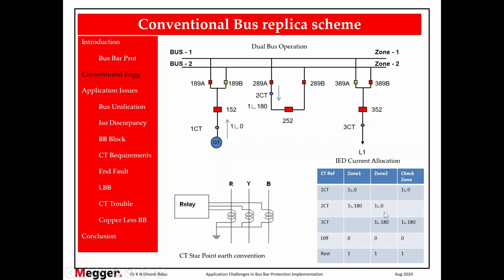So the simple concept is, in the bus coupler or bus section, if you are using only one CT core which is earthed towards bus 1, then in whichever bus it is not earthed, like in bus 2, where it is earthed away from bus 2, in that bus we will add 180 to it. So that means 1 angle 180, 180 plus 180, 360, which is again 0. That's how this 1 angle 0 appears here. This is the firmware logic which we implement in the numerical relays.